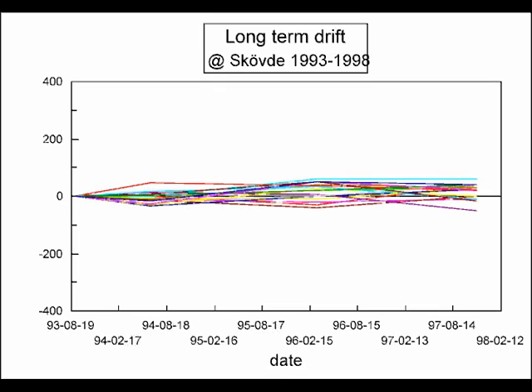And then we asked for historical information on the sensor. And we got the information that, hey, your counterparts, Siemens Europe, they've been using these things for a long time now. Siemens Asia, these things are in. But the clincher was the trend and historical data from a school in Sweden that showed that these sensors had been in since '93 and, in fact, still hadn't required calibration. And looking at the stability of these things. What it entailed ultimately was a lesson in NDIR technology from the supplier, in this case Global Controls.